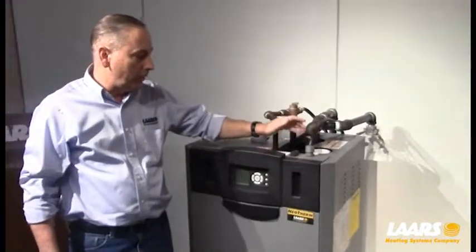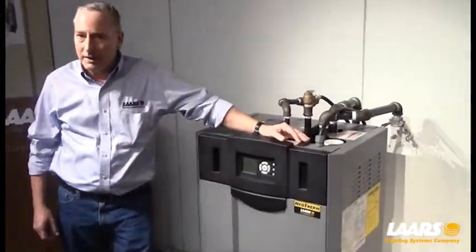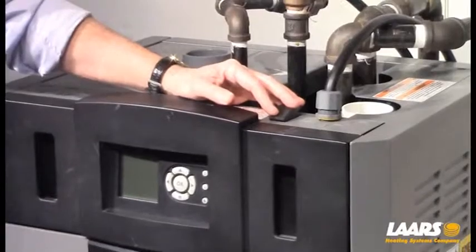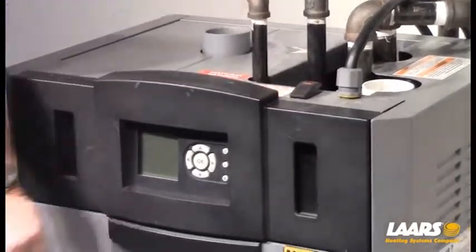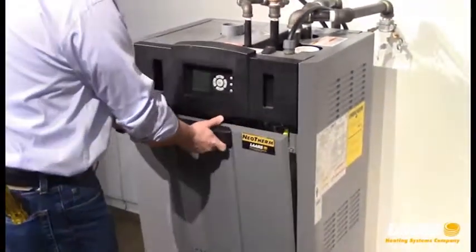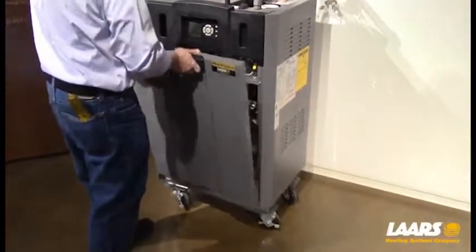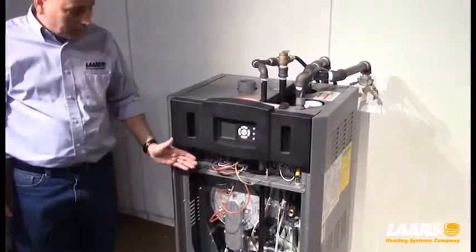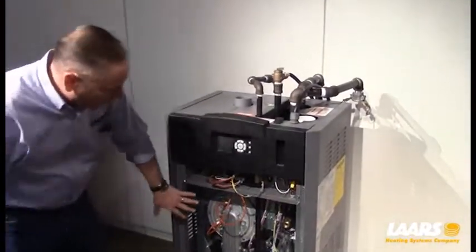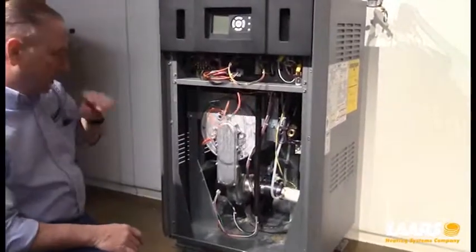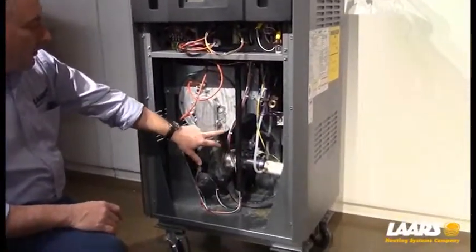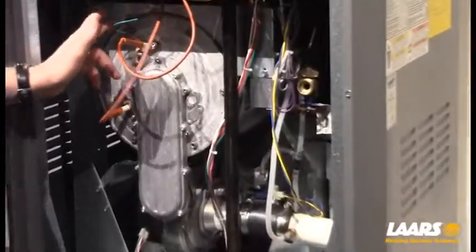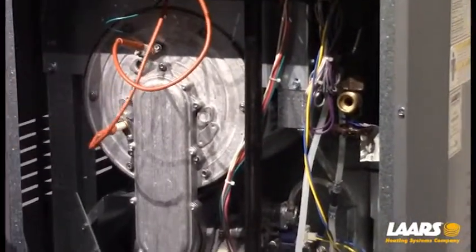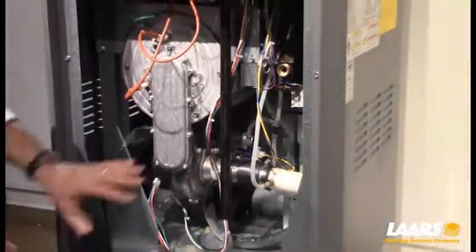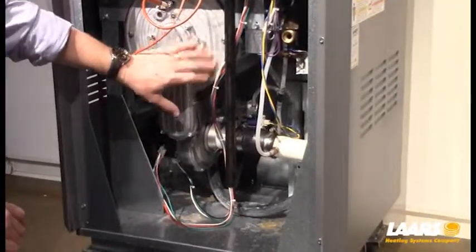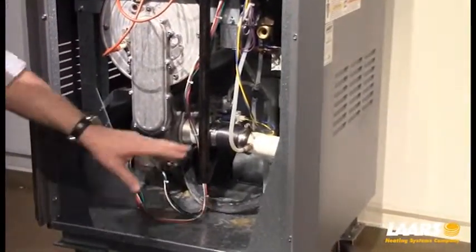So the very first thing we want to do is make sure power is off to the boiler and gas is shut off. Okay. We're going to remove the lower panel simply by pulling forward, lifting directly up. Now that the lower cover door is off, we're going to discuss getting into the heat exchanger itself. So you'll see there are 6 number 10 nuts that can be removed, and that whole burner plate will come out as one piece.